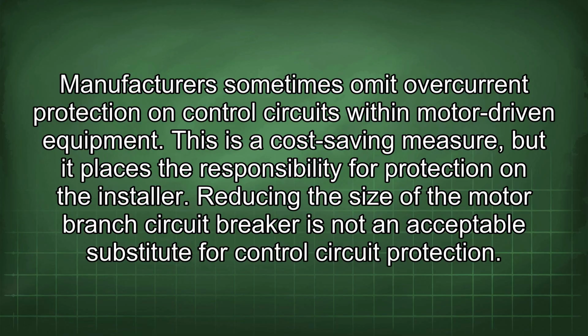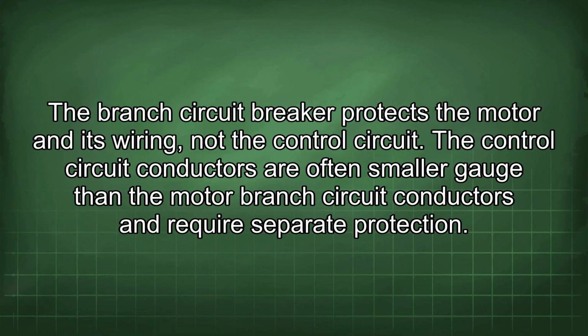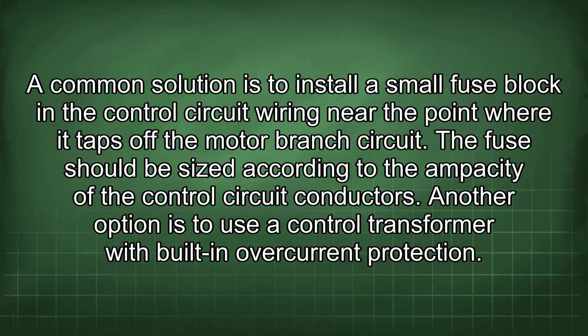Reducing the size of the motor branch circuit breaker is not an acceptable substitute for control circuit protection. The branch circuit breaker protects the motor and its wiring, not the control circuit. The control circuit conductors are often smaller gauge than the motor branch circuit conductors and require separate protection. A common solution is to install a small fuse block in the control circuit wiring near the point where it taps off the motor branch circuit. The fuse should be sized according to the ampacity of the control circuit conductors.